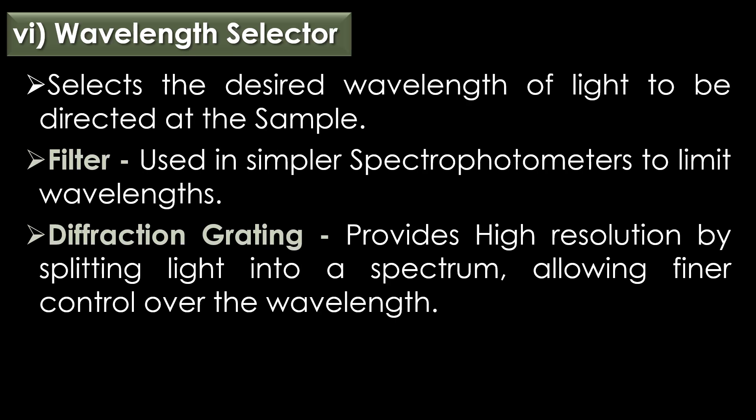Wavelength selector: the wavelength selector selects the desired wavelength of light to be directed at the sample. Filters are used in simpler spectrometers to limit wavelengths. The diffraction grating provides high resolution by splitting light into a spectrum and allowing finer control over the wavelength.